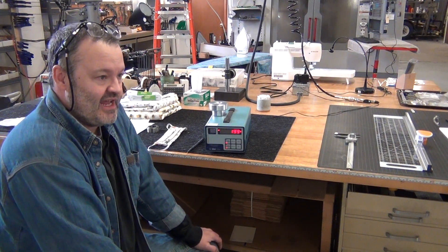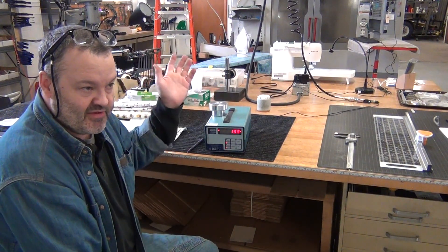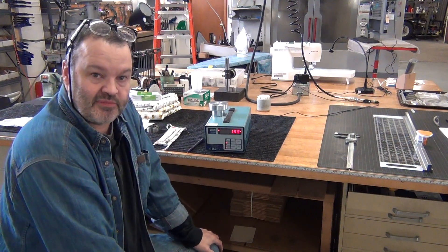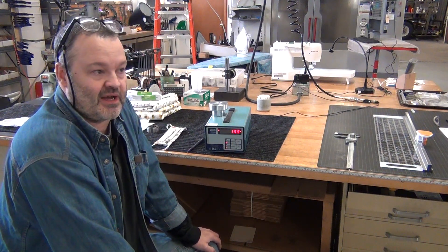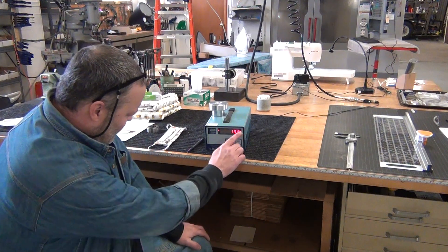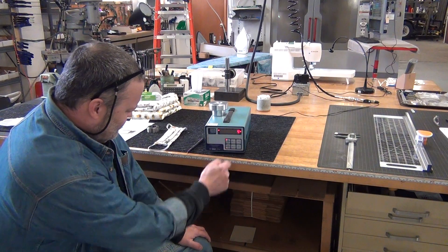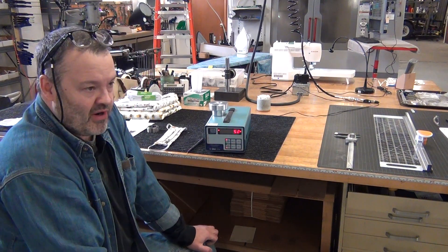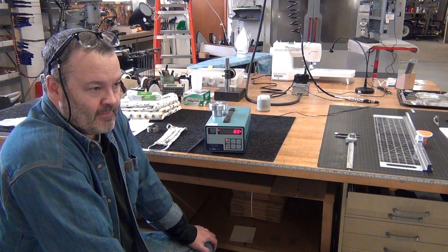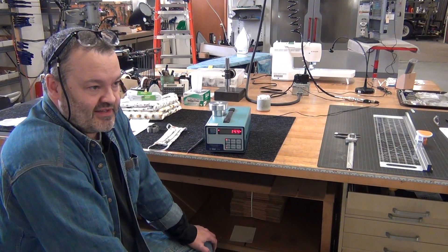This adapter I just have open to the air. We're in a shop — probably pretty dusty because it is a workshop after all. Let's go ahead and do a count at one micron. This will count for 10 seconds. Now it's counting particles one micron and larger, and this will give us a baseline for what the air quality is in this shop.